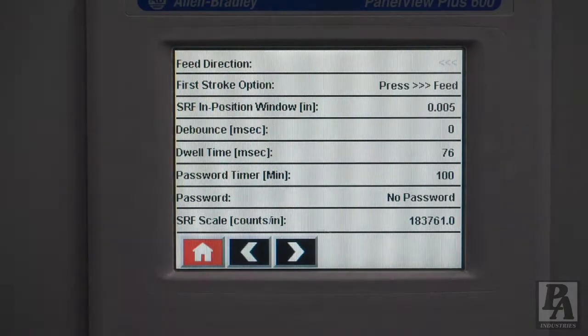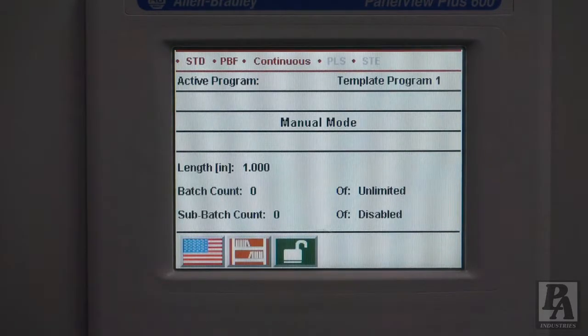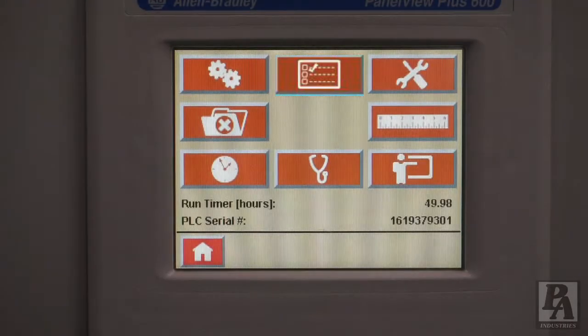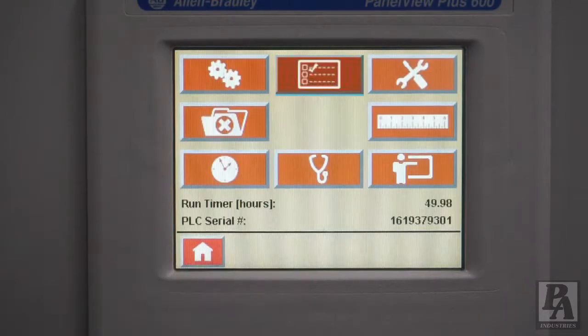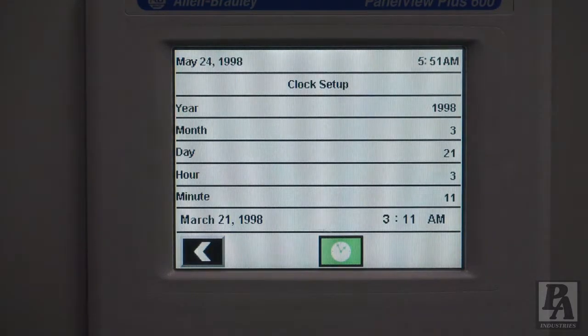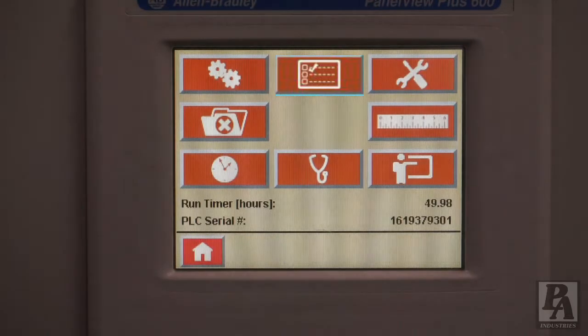In the feeder setup menu, you will be able to access feed direction, first stroke option, and other global parameters such as debounce and dwell time. In the fault history section, you will be able to see any faults that have occurred on the feeder along with the timestamp — this can be a very useful screen for debugging. The clock settings menu allows you to change the time and date; you should not change the clock settings while the machine is in auto mode, as doing so could cause issues with motion control.